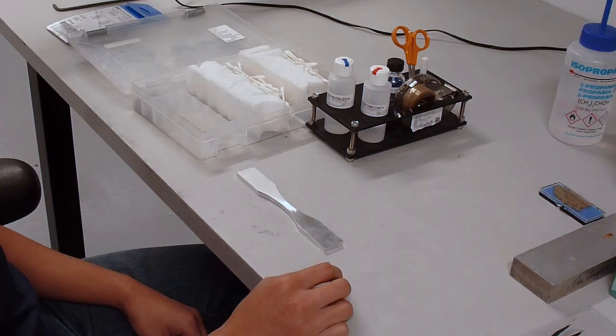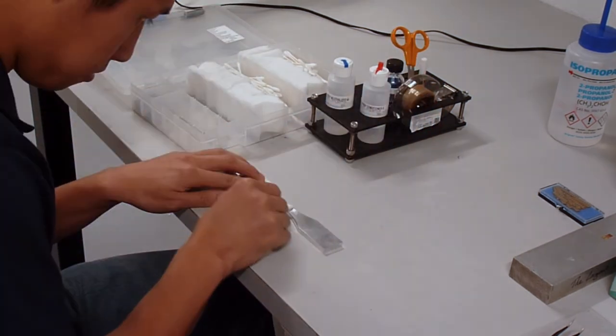The final task before the strain gauge can be applied is a secondary cleaning of the surface. Scrub the surface with the mild acid conditioner repeatedly using cotton swabs until one remains clean.